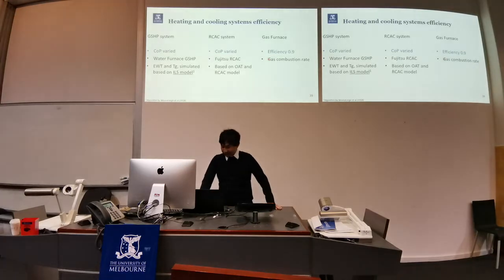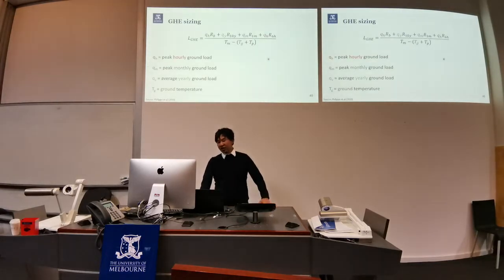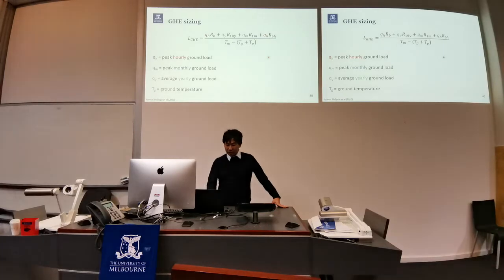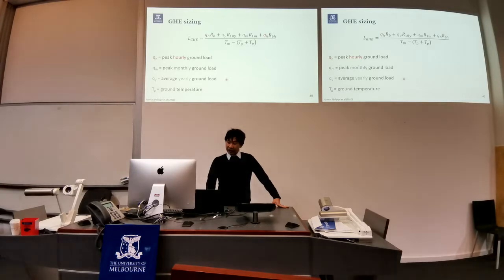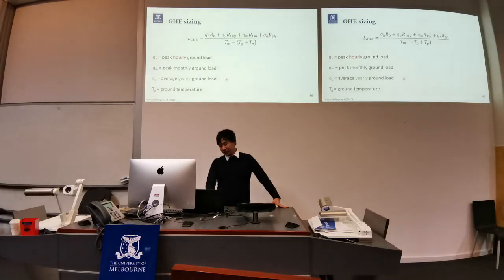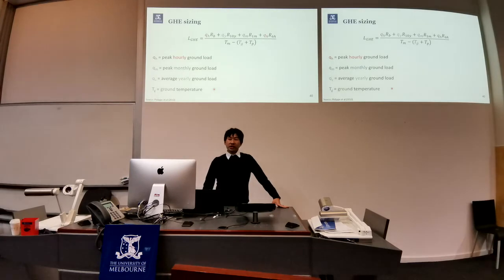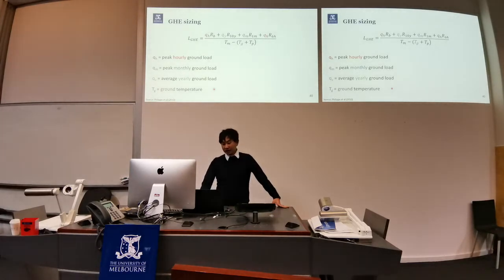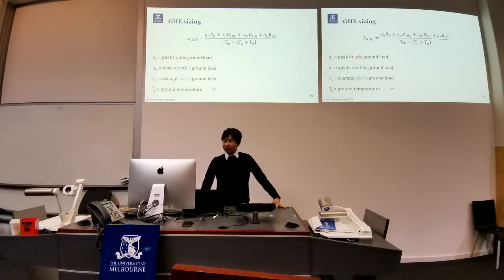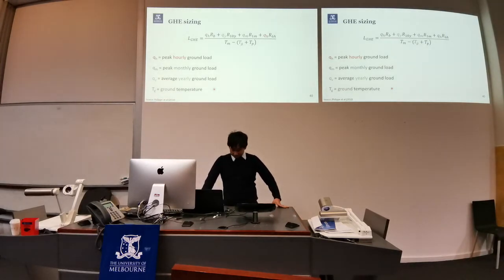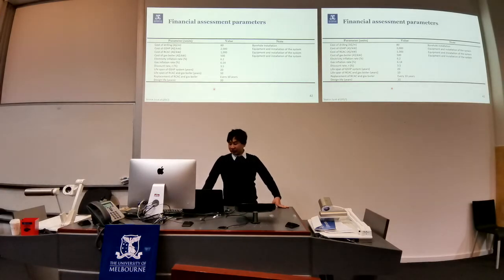The ground heat exchanger length component of the ground source heat pump system is calculated by using this ASHRAE design equation. The peak hourly, peak monthly, and average yearly ground load are calculated based on the weather data. The ground temperature is assumed as the mean air temperature plus 2 degrees Celsius, as recommended by the IGSHPA guideline. All other parameters are assumed the same between all cities for simplicity. All the installation costs are also kept constant, and this is based on the work by Lu et al., which represents typical installation costs found in Australia.